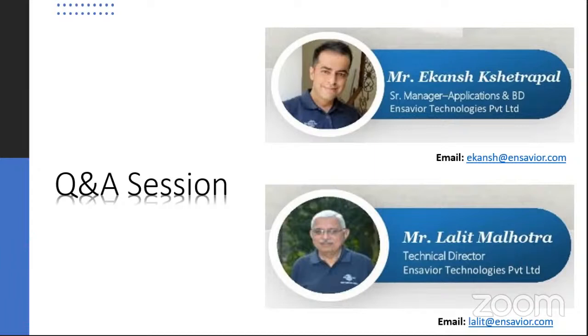How much energy saving can we have using TES? See, it is all application specific. I would say it's project to project. It is generally dependent upon your load profile. For example, if you have a very flat load profile throughout 24 hours, then it may not be very beneficial for you. But if you have a reasonable variation in the day hours or even in the 24 hours, like more load during the daytime and less load during the night time, and also you have differential tariffs, let's say a lower tariff at night time and a higher tariff during the daytime, so that advantage can also be taken.